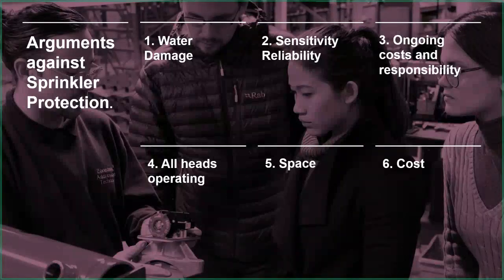Number 4, a bit of a classic here: all the heads operating at once. For me that's linked to water damage. People see this idea from the film and television industry, who want to create a bit of drama, and all the heads go off at once. That is not the case. Those in the know understand there is such a thing called a deluge system, where you do get all the heads operating, but a deluge system is not going to be installed in a car park, a school, or a residential building. It's just not going to happen.